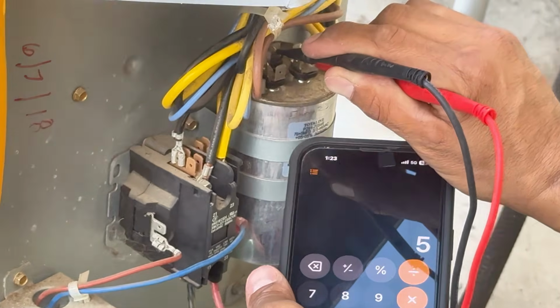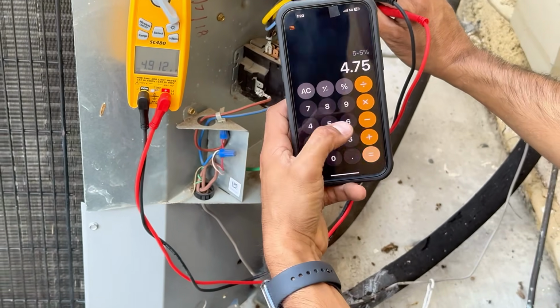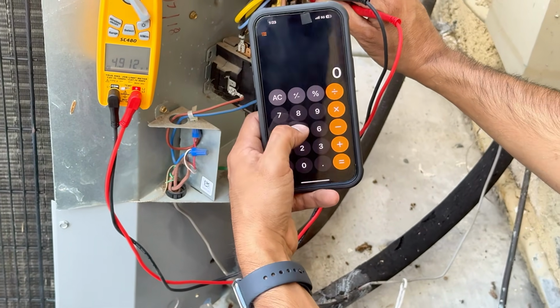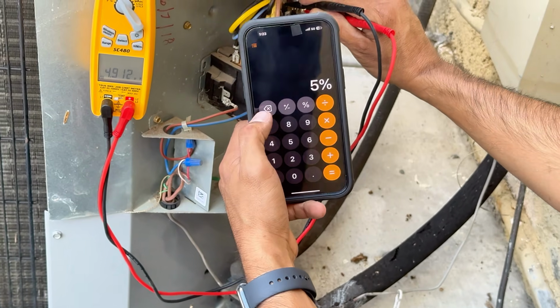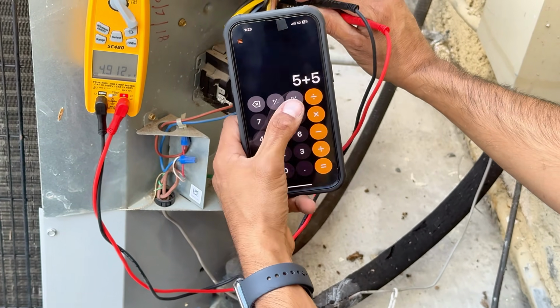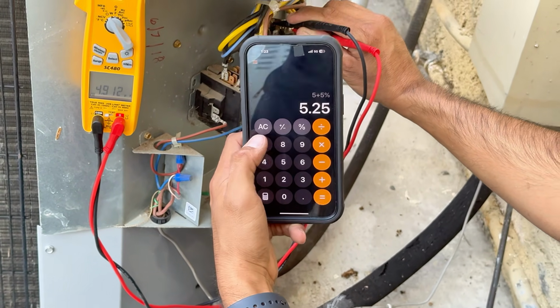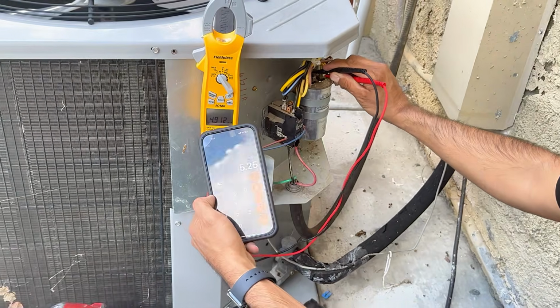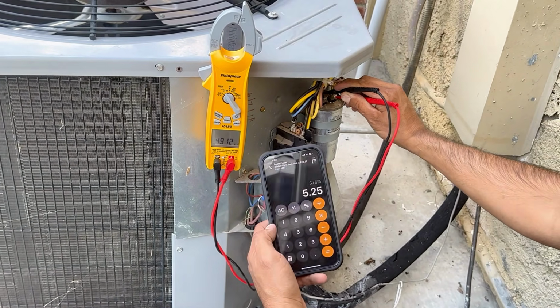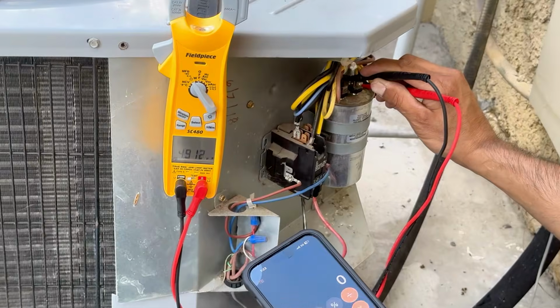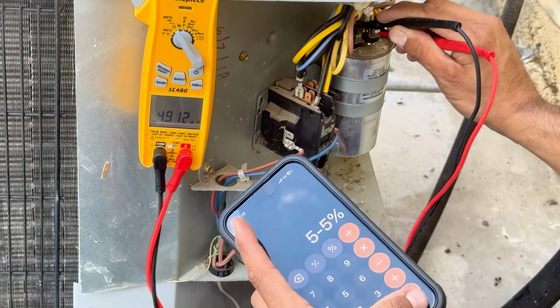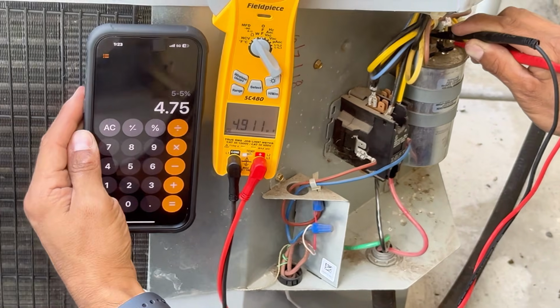The little one, 5 microfarad, that's for the condenser fan. 5 minus 5% is 4.75, and 5 plus 5% is 5.25. So the range is 4.75 to 5.25. I'm within range, at 4.912 right now. So I'm good, my capacitor is good.